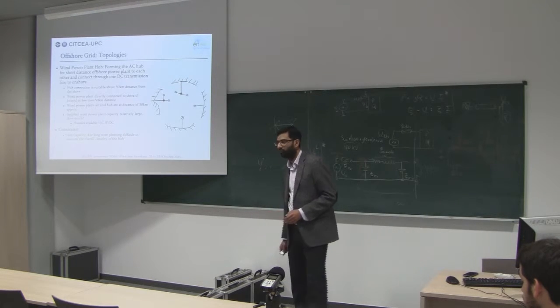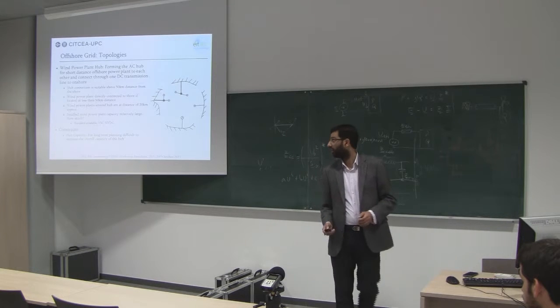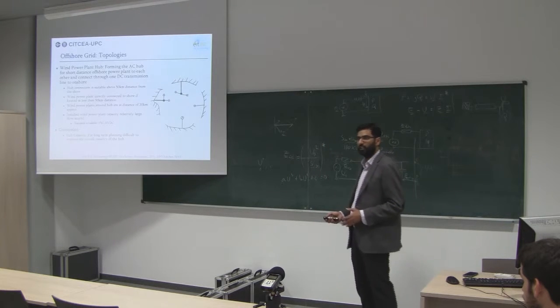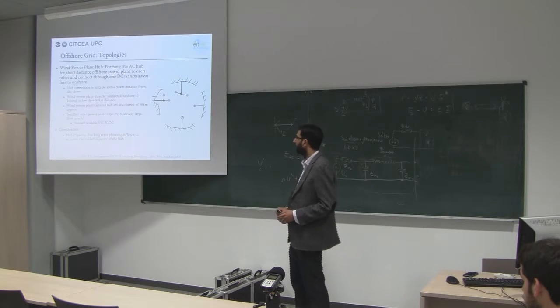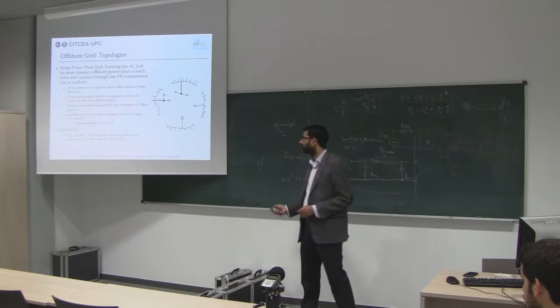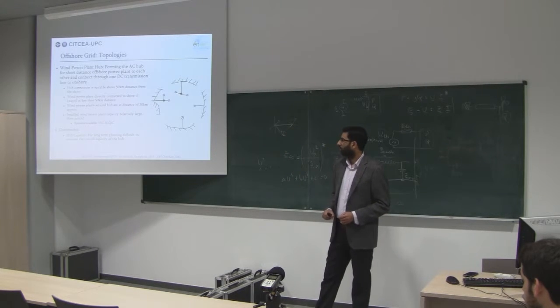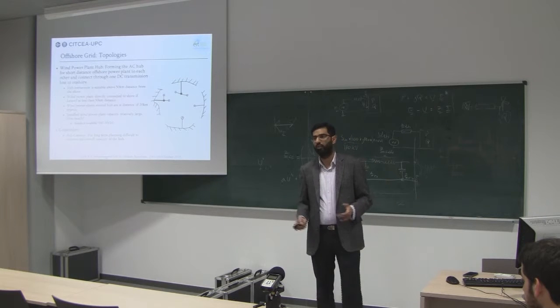If it's far, then it's better to have a separate connection. Now the question is, what will be the capacity of this transmission line? We are still limited by the standard available VSC HVDC system, so we cannot increase the capacity. For long-term planning, the biggest constraint is how to design the capacity of this hub.